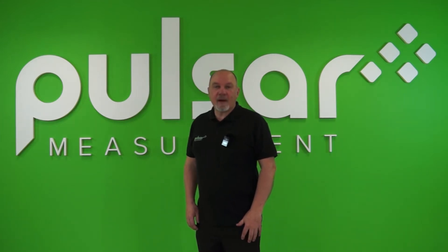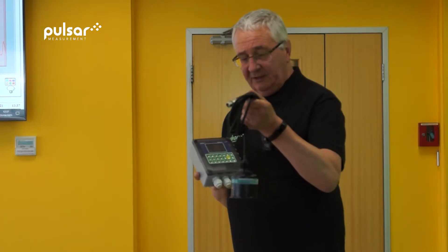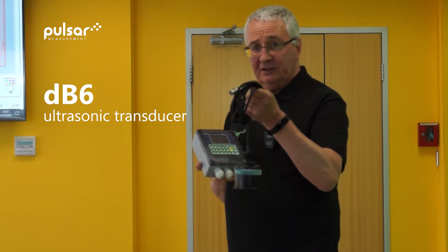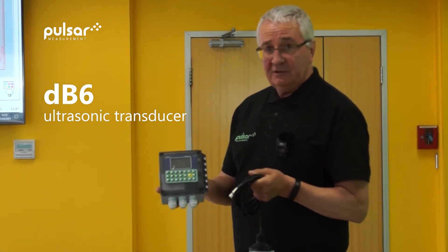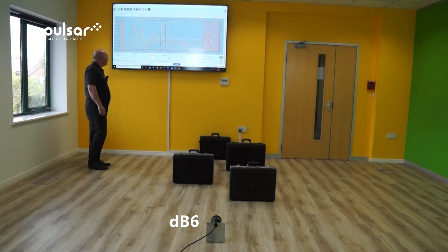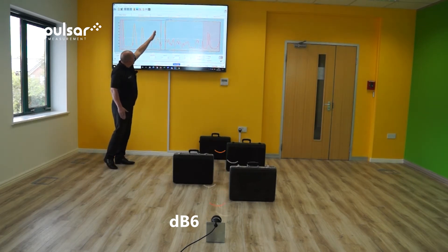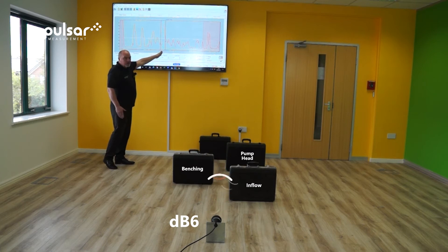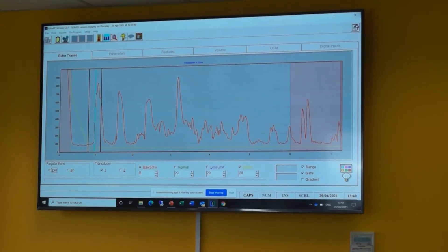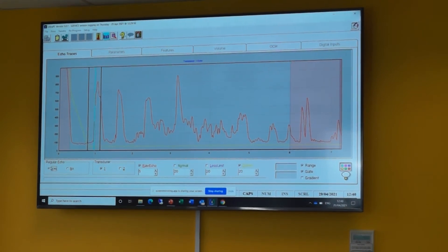To demonstrate this, we'll carry out what's become known as the briefcase stance. We're using a DB6 6-metre range ultrasonic transducer, coupled with our latest Ultra 4 transceiver. You can see on the floor the DB6 transducer is positioned and it's actually firing through the briefcases, which represent the fixed obstructions, to the bottom briefcase which represents the empty level. On the screen, you can see the echo profile coming back from the Ultra 4, which shows the distinct echoes from all of the briefcases.